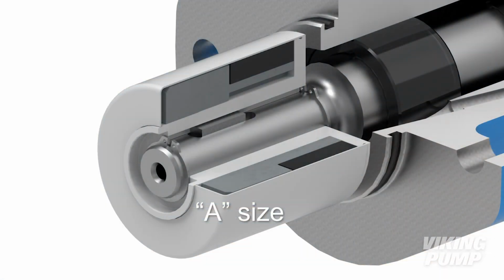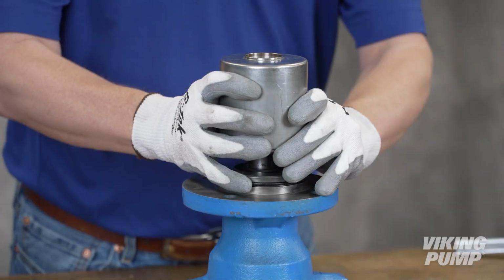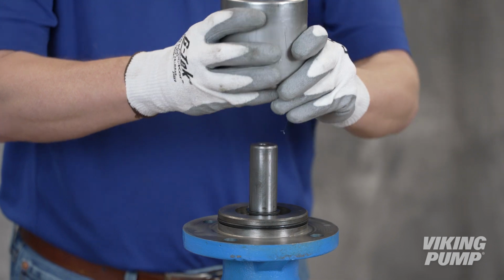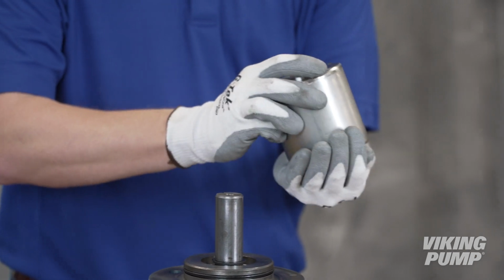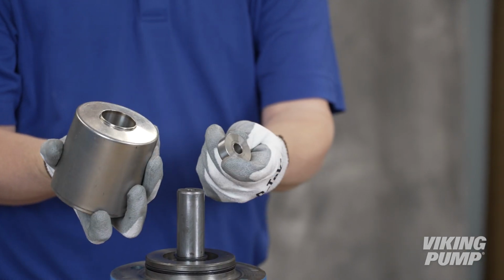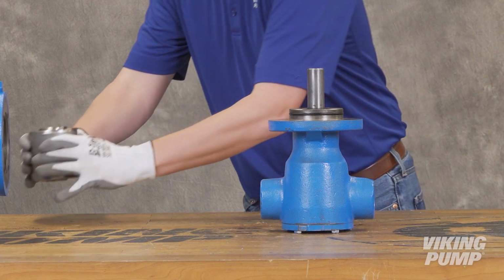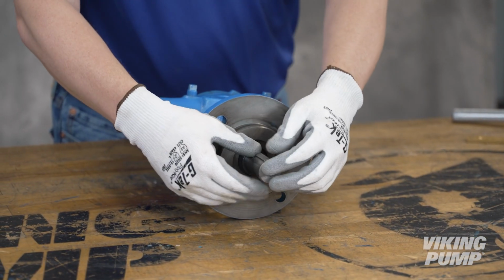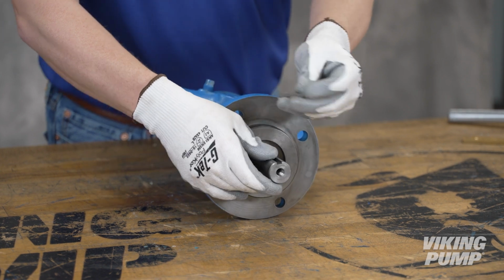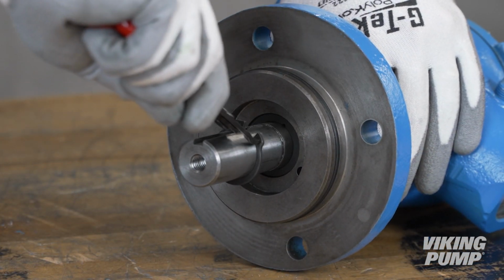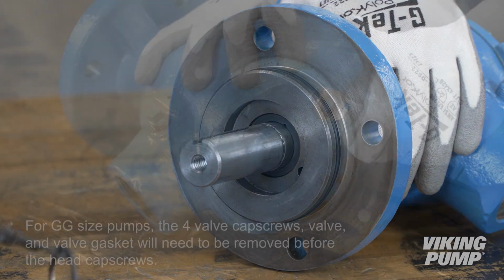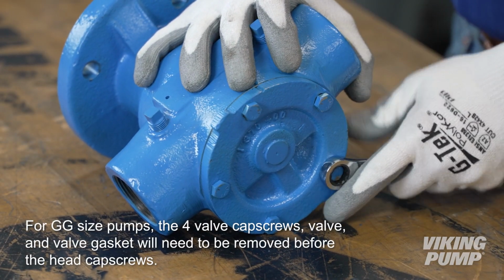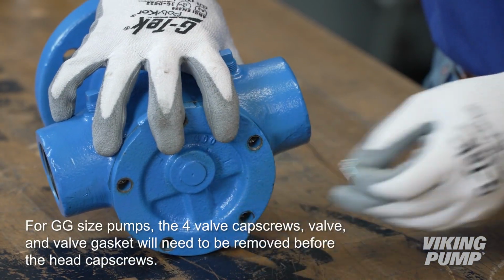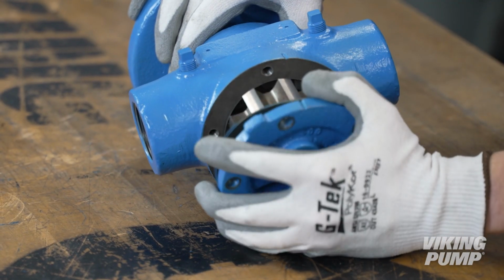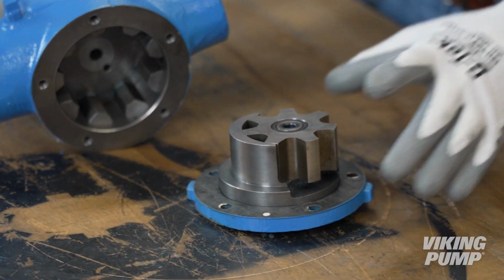For A-size magnets, remove the retaining ring from the end of the shaft to remove the inner magnet. Slide the inner magnet off of the pump shaft and remove the washer. Again, use care when setting this powerful magnet down. If pump disassembly is required, remove the shaft key and retaining ring. Loosen and remove the head cap screws. Remove the pump head. Be careful not to allow the idler gear to fall from the head of the pump.